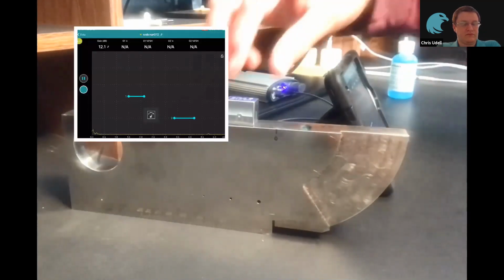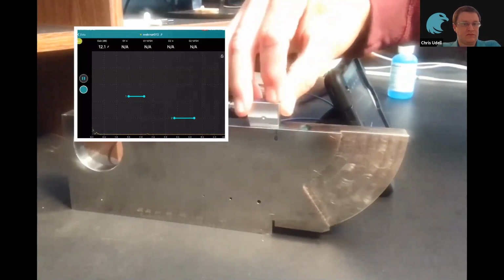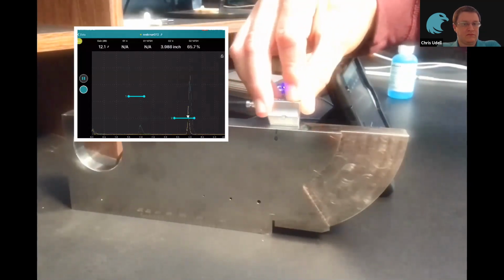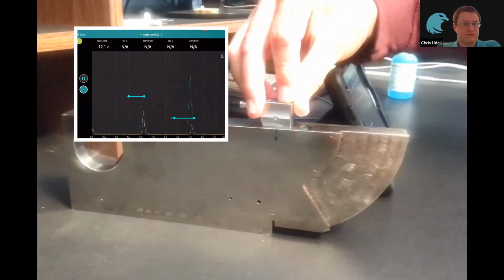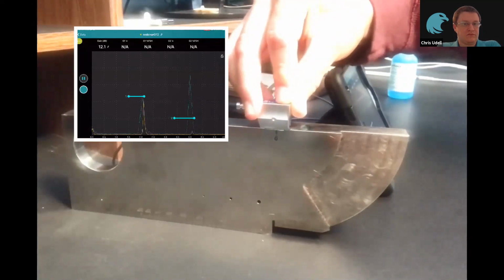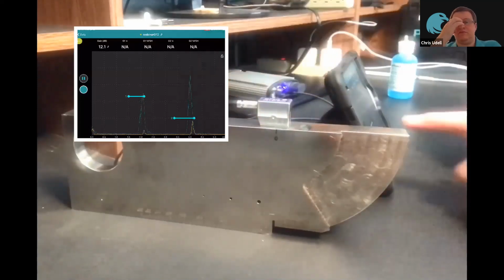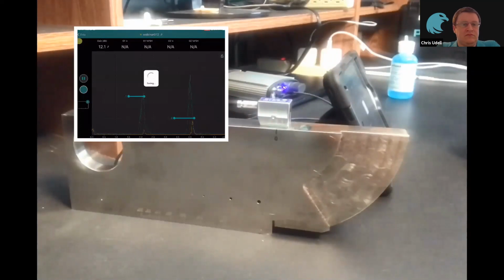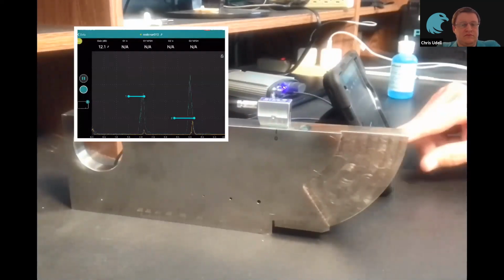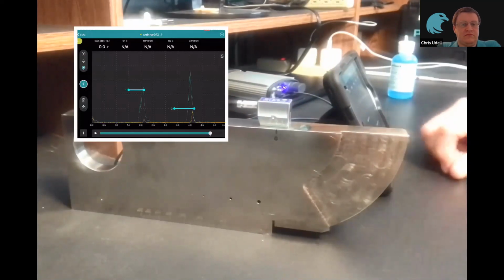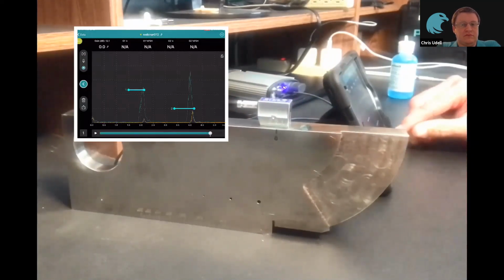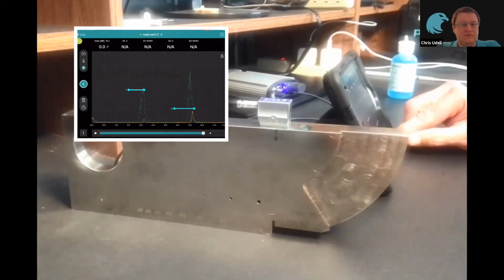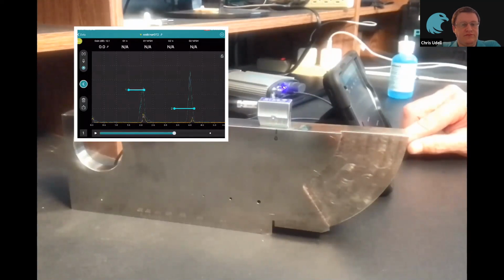So as I start the inspection, I go over and I go across my peak. Now you can see I can capture peaks with the peak memory, but sometimes duplicating that peak can be a little bit challenging. So if I just tap the record button, now I can go back into my review mode, and since we're recording the full data set, I can just go back through my full data set, scrubbing and slowly seeing where my signal is going to match up with that peak indication.